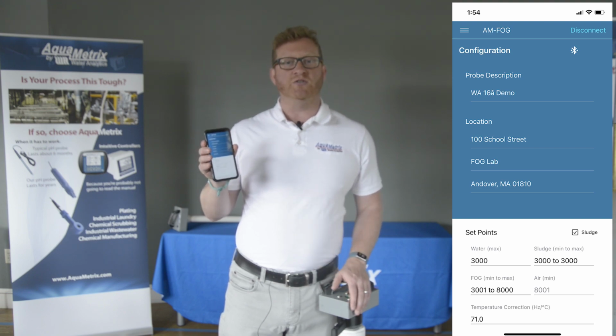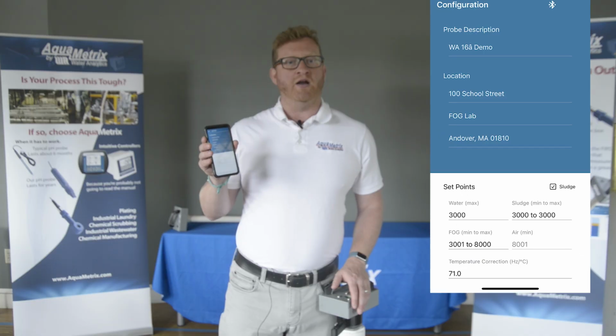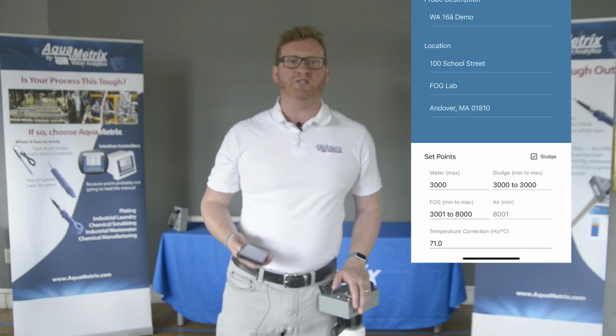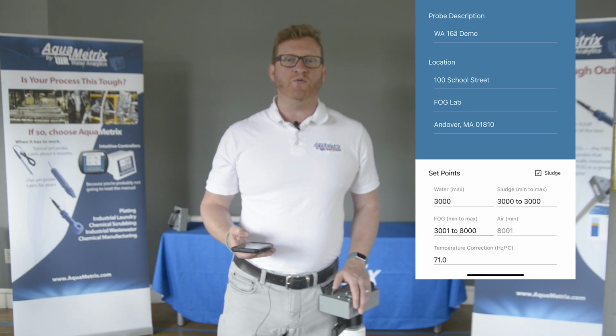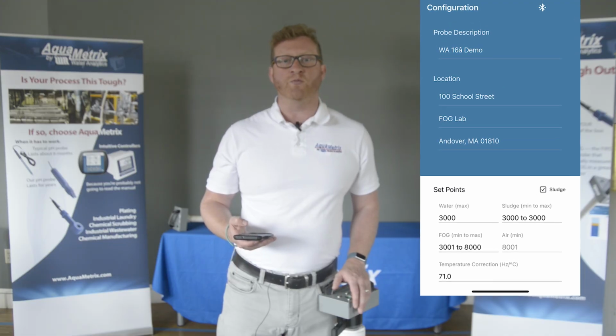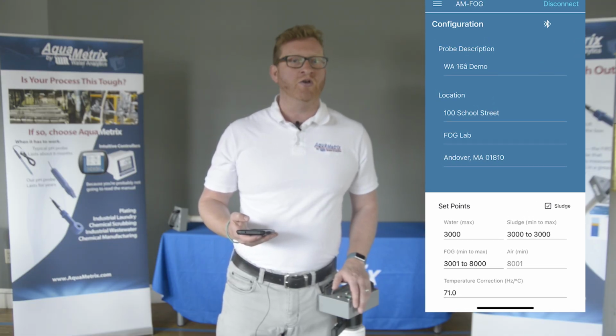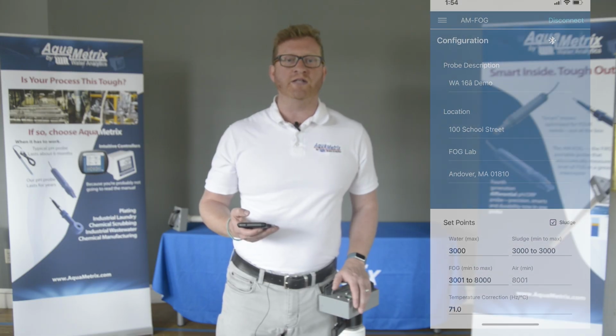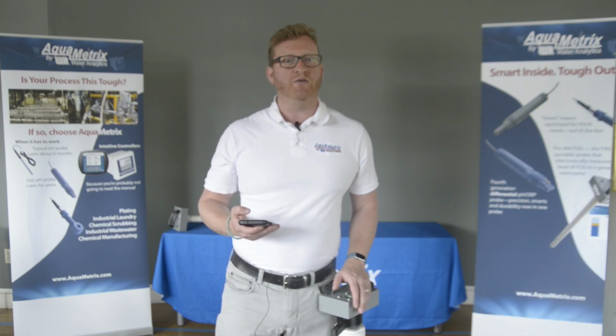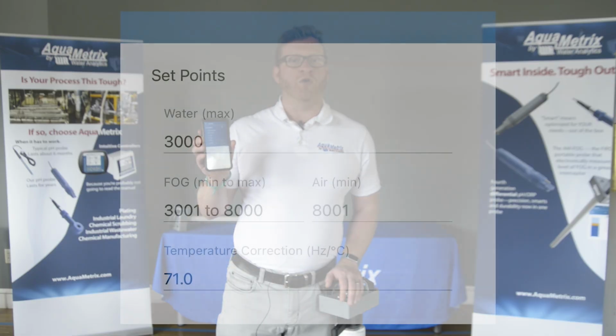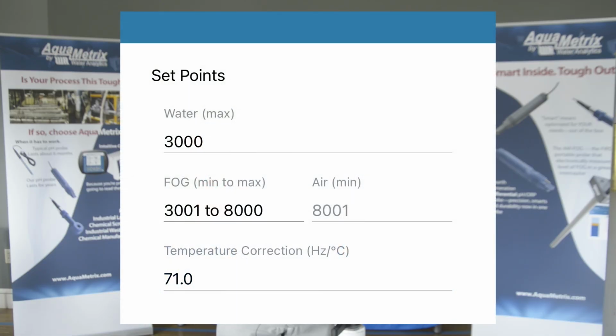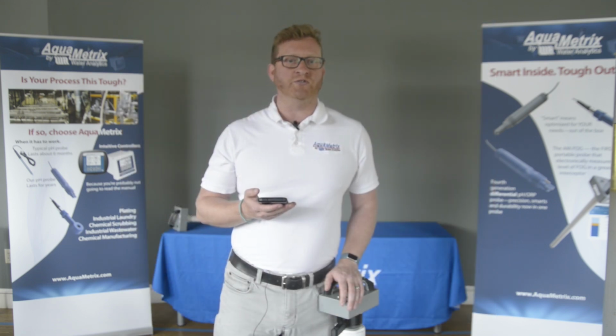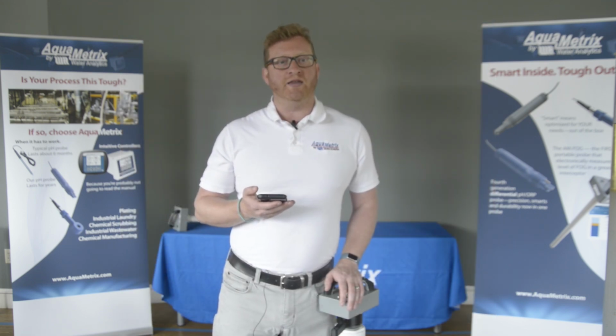The bottom of the screen shows a sequence of numbers. These define the range of values that correspond to water, fog, air, and if you enable it, sludge. The probe's electronics sets arbitrary values of 0 for water and 10,000 for air. Fog is somewhere in between, roughly 3,000 to 8,000. We are still working on an algorithm that will accurately and consistently measure the thickness of sludge. Typical values are between 1,000 and 2,000, but stay tuned for more information on sludge. Here's the screen showing the set points for water, fog, and air. As you gain familiarity with the probe readings, you will adjust these numbers for the interceptors in your jurisdiction. More about that in the next video.